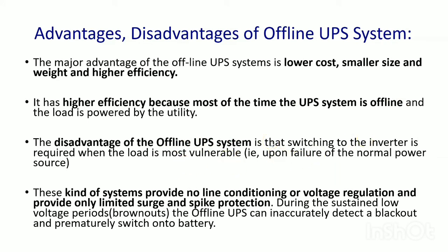The disadvantages of offline UPS include switching time, which can be problematic in critical applications. These systems provide no line conditioning or voltage regulation and offer only limited surge and spike protection. In online UPS, protection from surges and voltage spikes is available, but offline UPS — normally being in offline mode — cannot protect against such mains line disturbances.